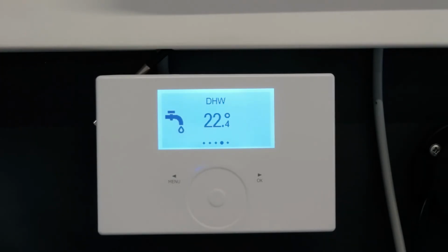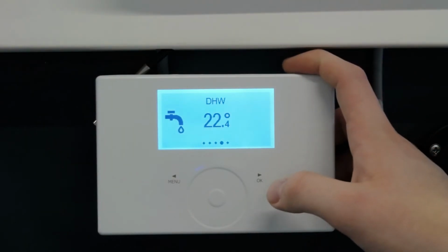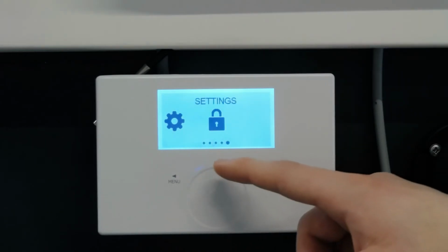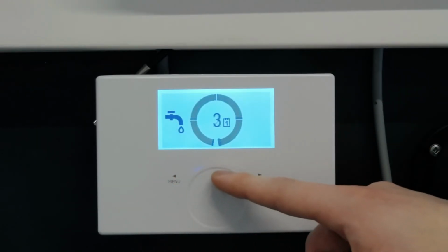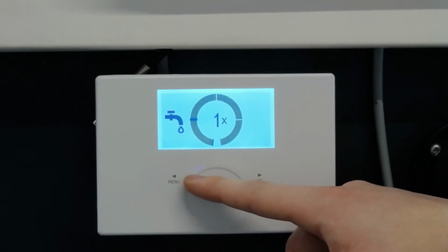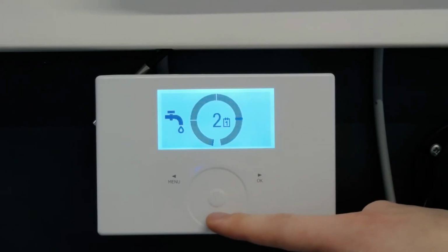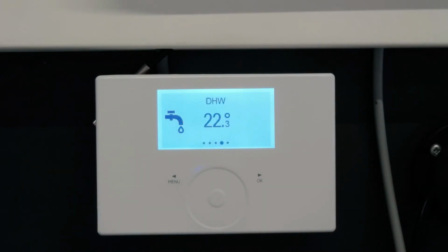If you would like to start the heat up program for domestic hot water, move the touch wheel, and then you can say how often the storage tank should heat up to the comfort temperature: 1 time, for 1 day, for 2 days, or for 3 days. So this is what you can set here, if you have, for example, no domestic hot water program, or if the tank is cold at the moment and you need warm water.